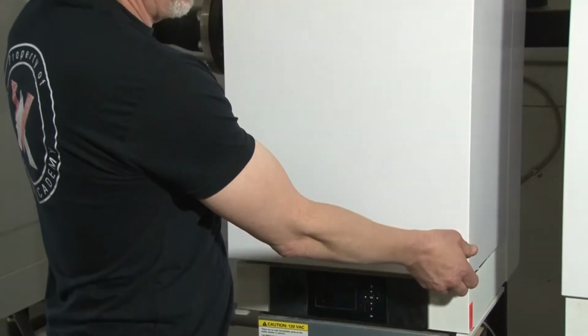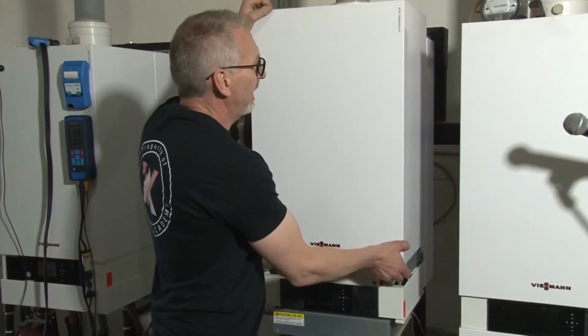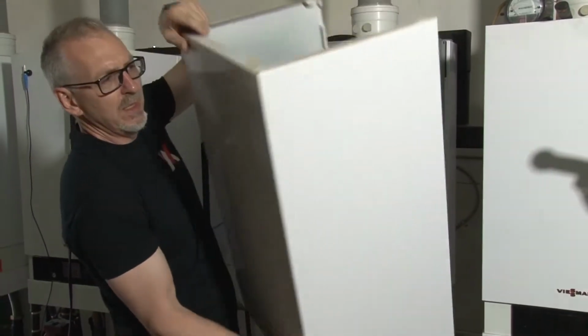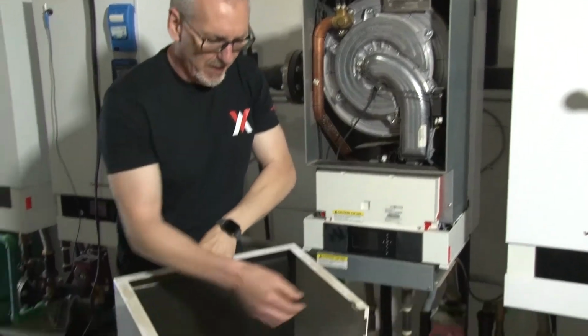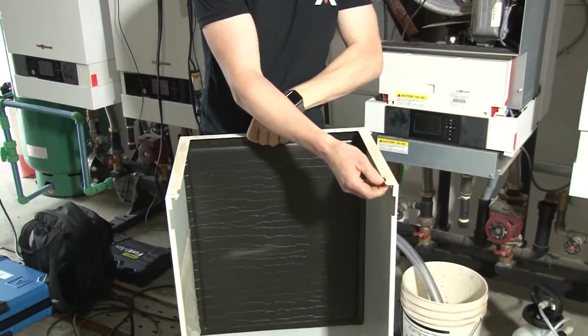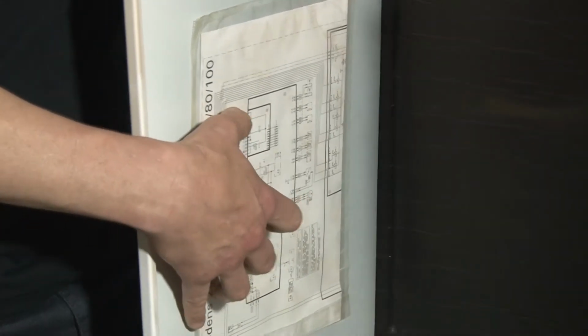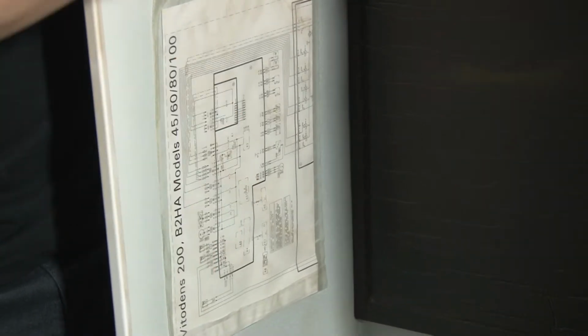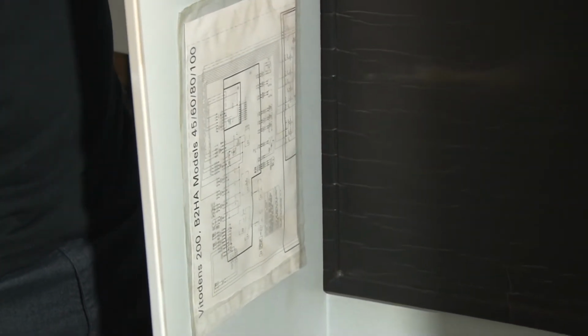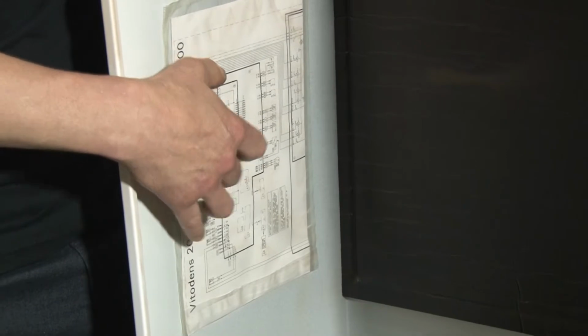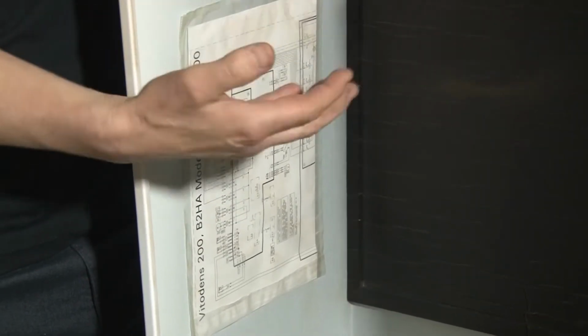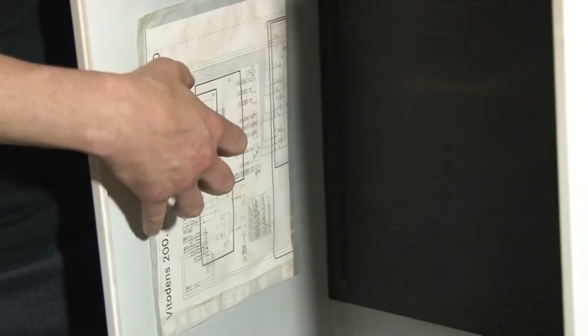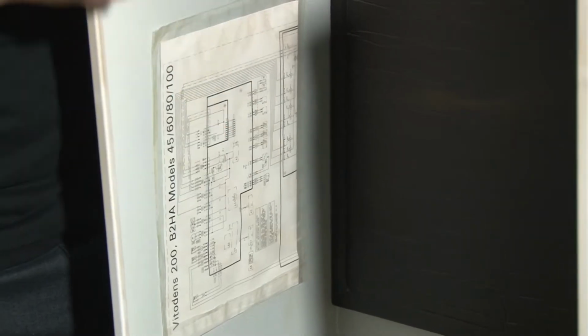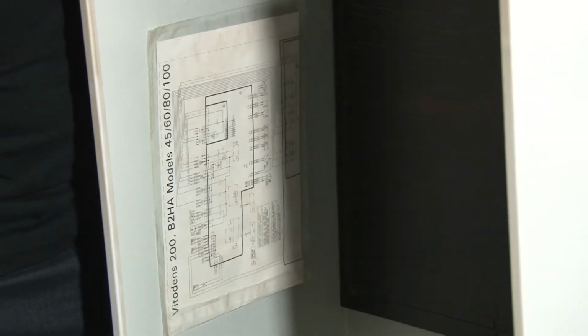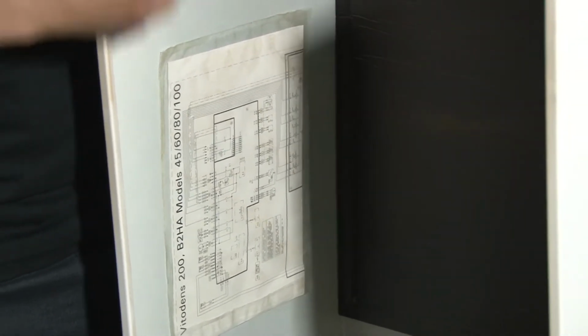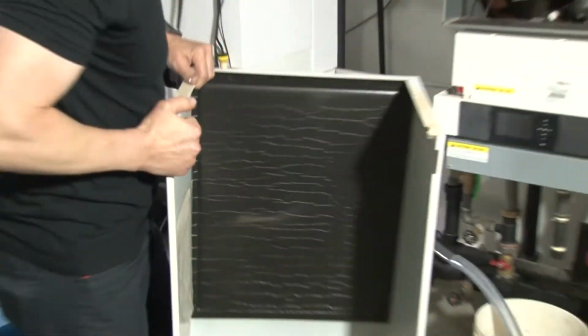Important not just to grab the door and pull it. When I lift it up and move it this way, these little plastic clips on the top here of your boiler are not going to break. If you're ever troubleshooting the boiler, a lot of times you might not have the service manual, you might not have access to information, but there's always this little packet here that'll show you how these boilers are wired. And we would expect things like pumps and different inputs, mixing valves and stuff to be wired if they have them in the system. So that little schematic is there just for you.